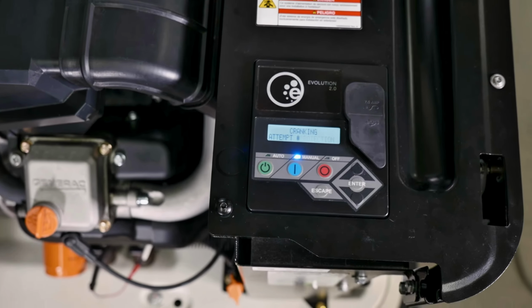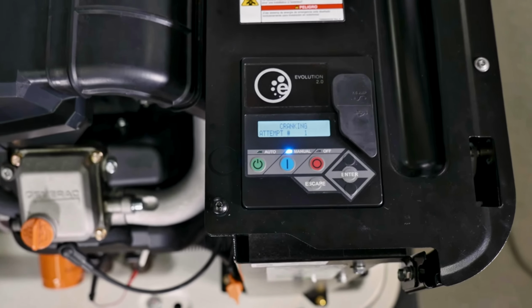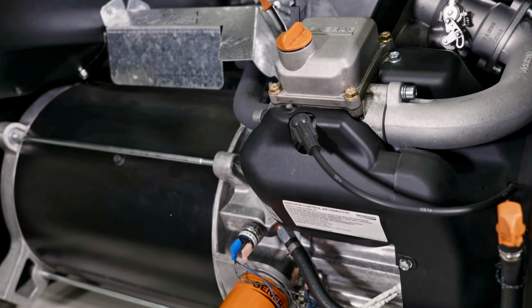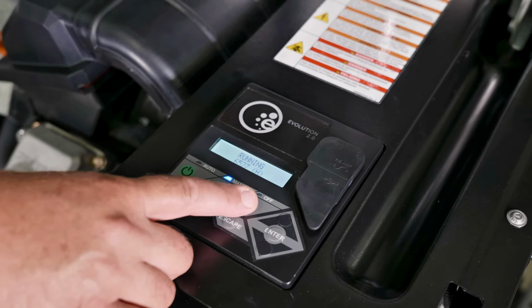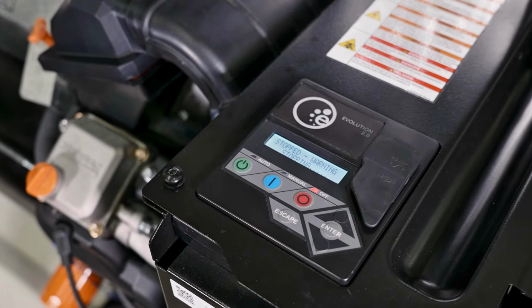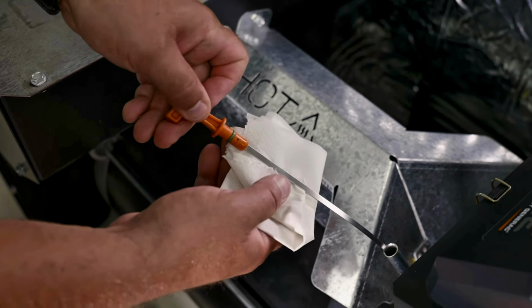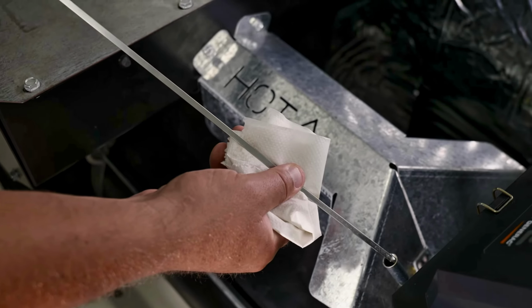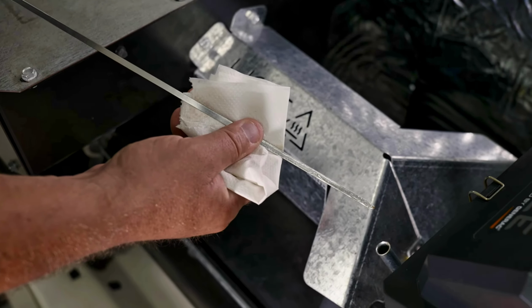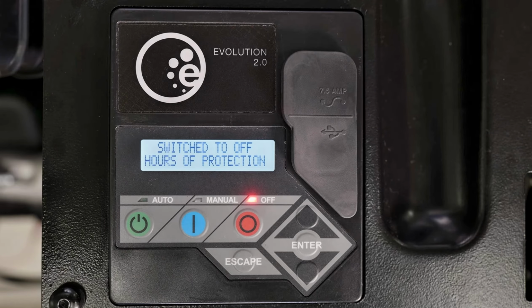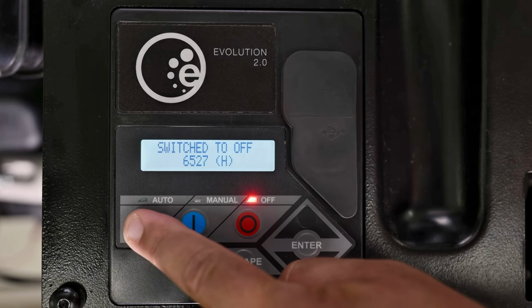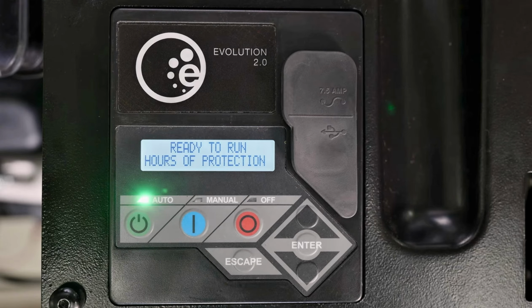Then press the manual button on the control panel to start the engine. Run the generator for 1 minute and check for leaks. Press the off button on the control panel to stop the engine and wait 5 minutes. Inspect the oil level using the oil dipstick and a clean cloth. If needed, add more oil but do not overfill. If the generator was not currently running due to a utility outage, simply press the auto button and close the lid.